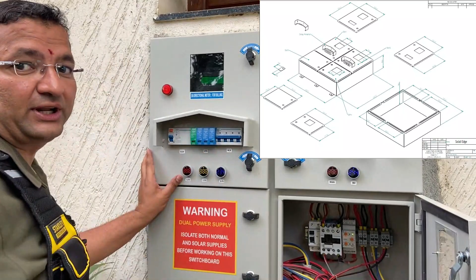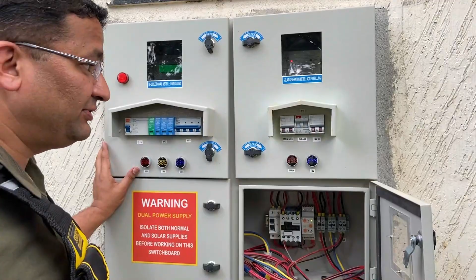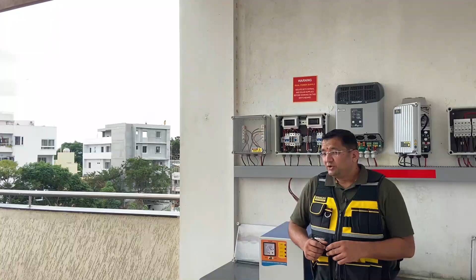Just to repeat, we have got a 3-phase meter, 3-phase protection. One phase from here is tapped. It first goes into an ELCB, over voltage under voltage protection relay, and then gets into the inverter through another level of protection. So we saw in the mains of the house, the main distribution panel of the house, the incoming DISCOM power goes through, because since it's a 3-phase input to the house, we have a 3-phase SPD, a 1+2 SPD, a 3-phase ELCB, a 3-phase MCB.